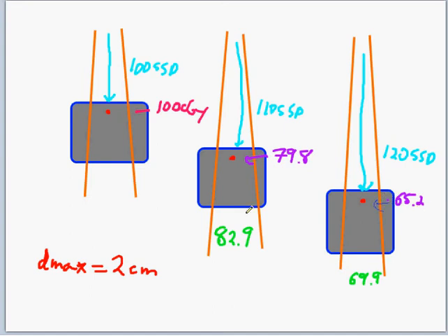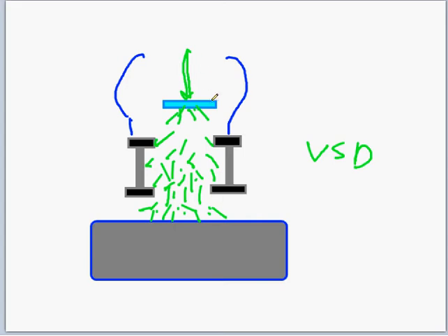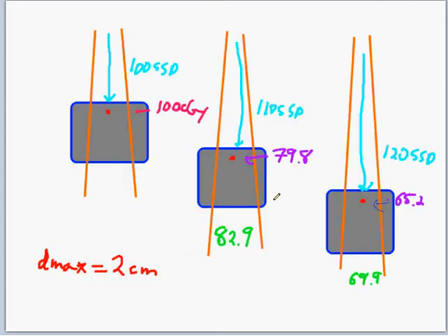And the physicists would say, well, inverse squared isn't working, but if I would pretend that the source of the electrons was not here at 100, but, in this case, they just do it mathematically and say if I would assume that the SSD was, instead of 100, let's say 82 in this case, and I'm not going to go through the math of how you figure that out, but they just use the measurements they take and say if I would assume an SSD of 82, these would match pretty closely to what I would expect.